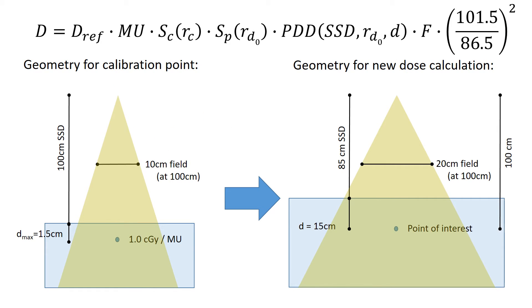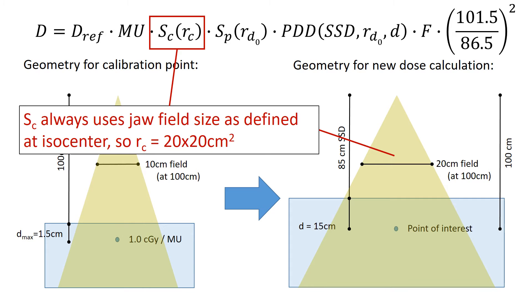Next, we're going to look at our scatter factors. And first, we'll look at collimator scatter factor. Collimator scatter factor always uses the jaw's field size as defined at the isocenter. So it's going to be equal to 20 by 20 cm, since that's the new field size.